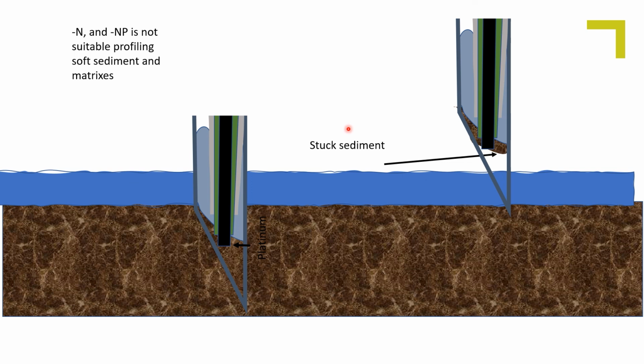This material will influence the redox potential measured in other layers, and the measurements might not reflect the real redox potential value. The material stuck in the needle tip might be very difficult to rinse away after use. For profiling in soft sediments and biofilms, we strongly recommend using non-needle protected sensors and electrodes. It applies to all types of needle sensors and electrodes.